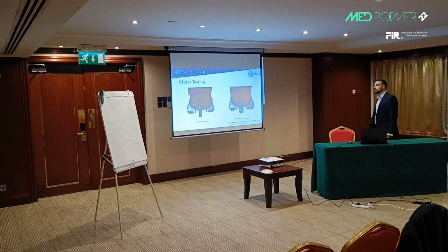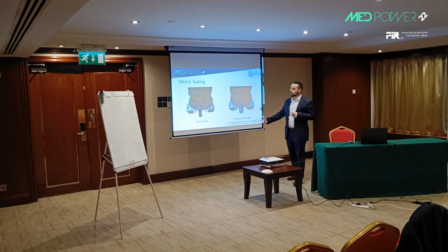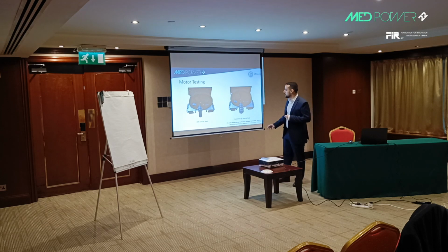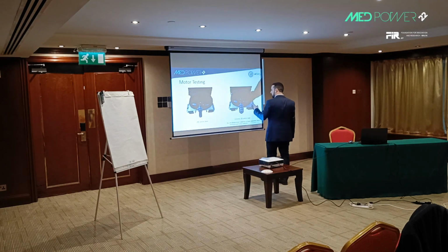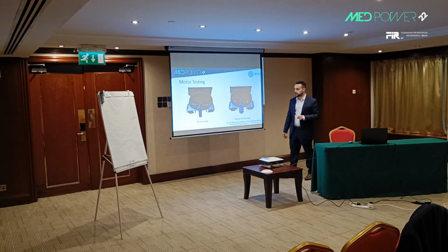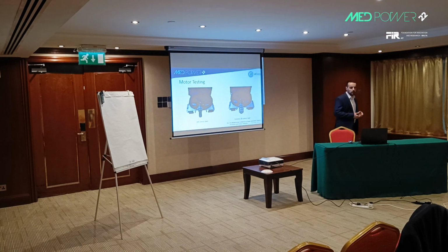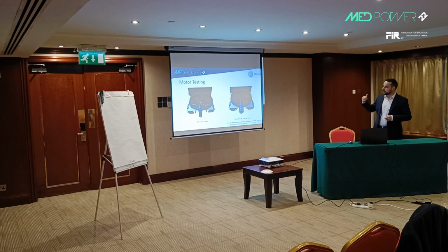Then we tested the motor to simulate an off-centric load. This will simulate a bearing fault, which is the most dominant fault on these induction motors. We used an off-centric load, which is quite small, and we also tested with an extreme off-centric load to see the differences in performance of the motor current signature analysis and the vibration analysis that we did.